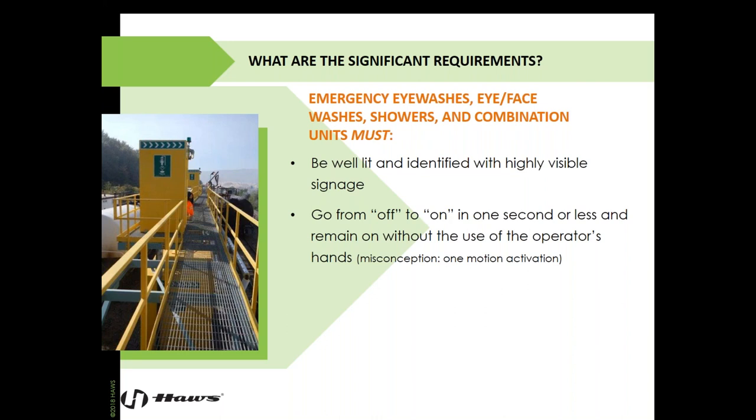Again, off to on. There is a misconception out there that it's one motion in the standard, and that comes down to state requirements. There are a handful of states that require one motion activation, but the majority of us have to comply with off to on in 1 second or less.